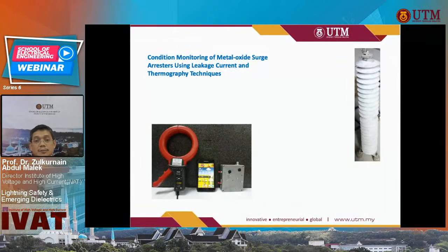So for the power system, we have what we call lightning protection for expensive equipment, for example the transformers at the substation. Surges can still go into the station through the lines, so we need to put arresters near the transformers, or in the case of transmission lines, we need line arresters to reduce flashover rate or back flashover problems.